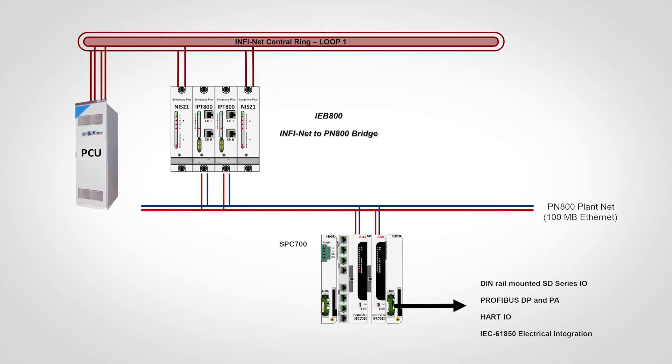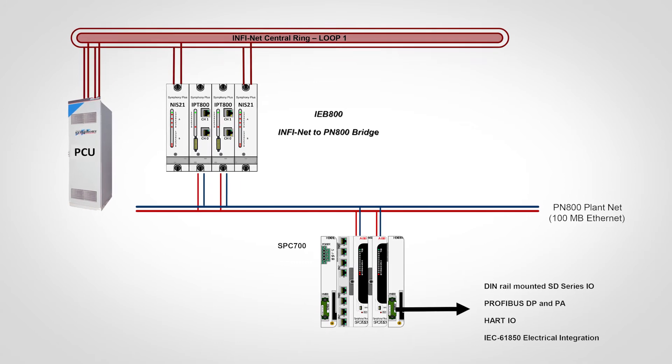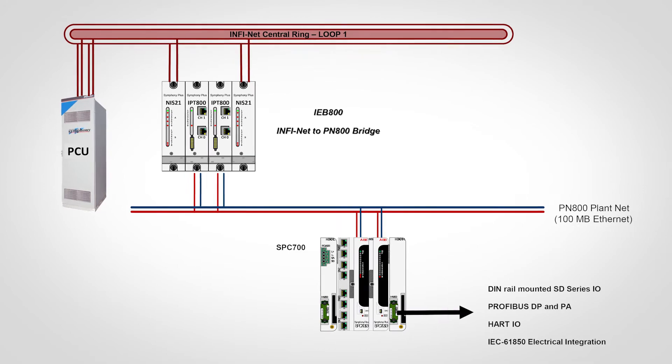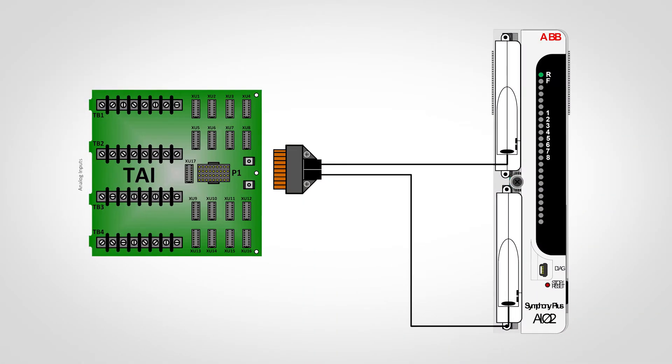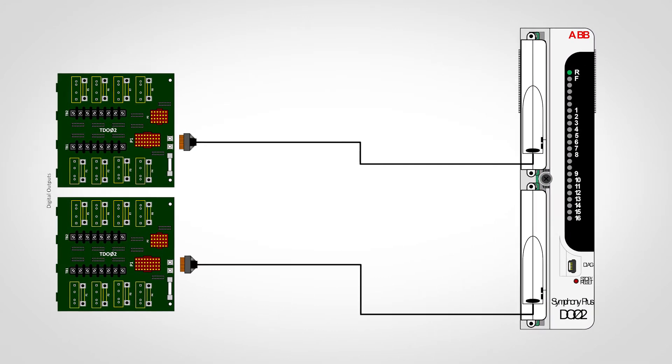The IEB800 Infiniti to Ethernet Bridge seamlessly connects Infiniti to PlantNet to provide bi-directional communications, much the same way as an IIL-02 local bridge connects satellite INFI-Net rings to the central INFI-Net ring. The IEB800 enables you to expand your existing INFI-Net or Harmony system easily and cost-effectively using the latest SD Series hardware. Changes to existing field wiring should be kept to a minimum, as reterminating field wires can be error-prone, time-consuming, and costly.